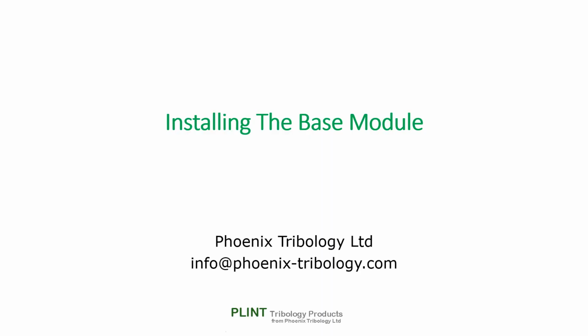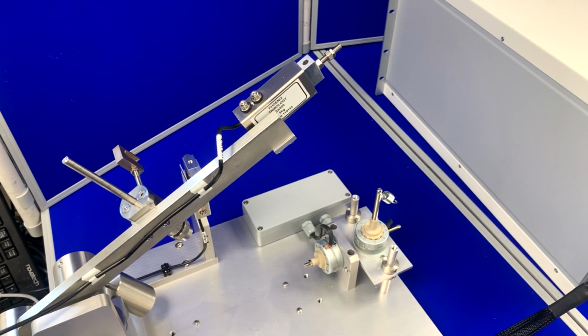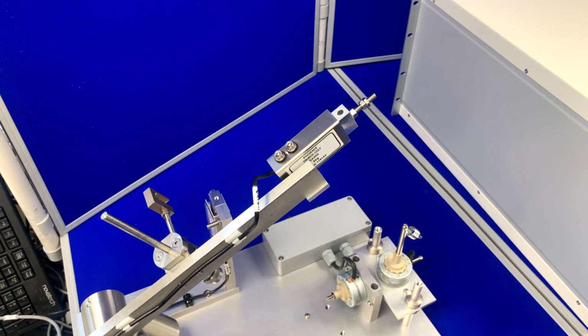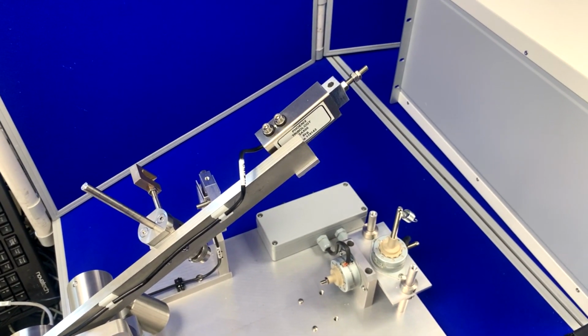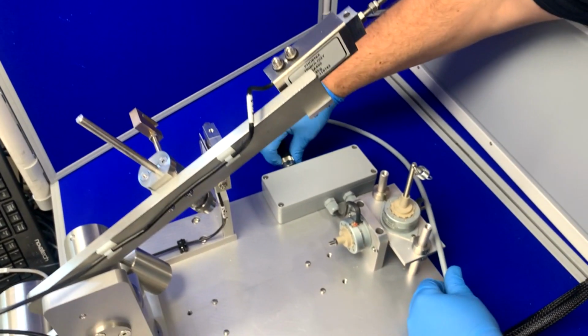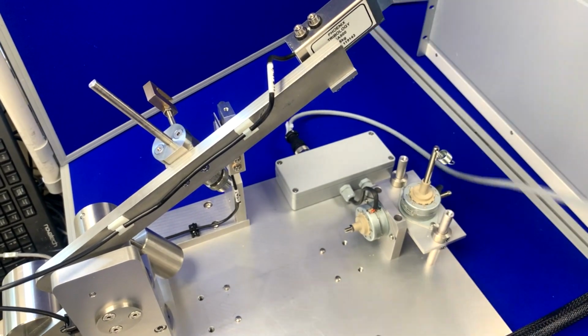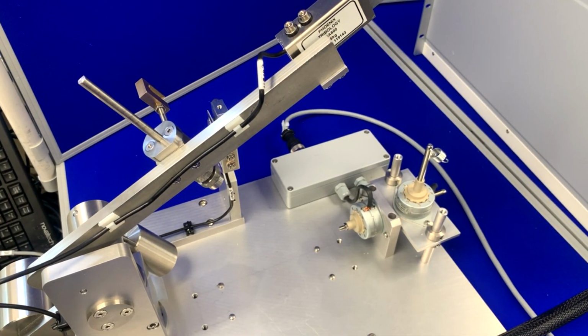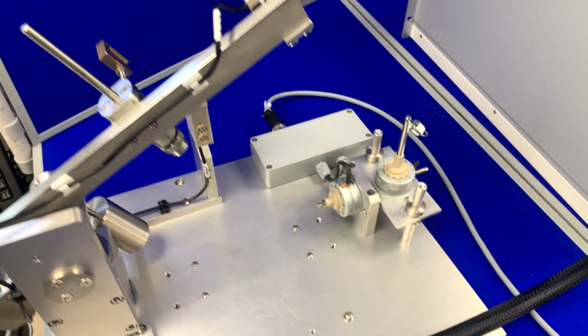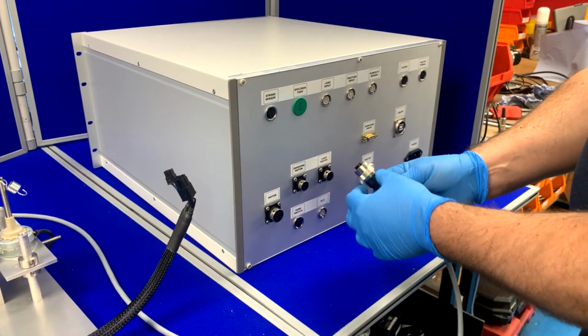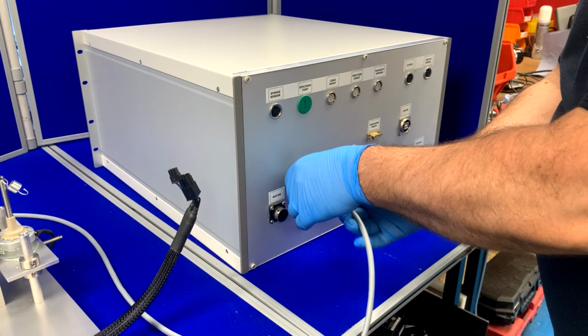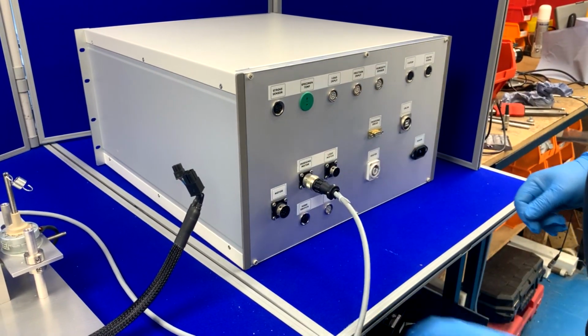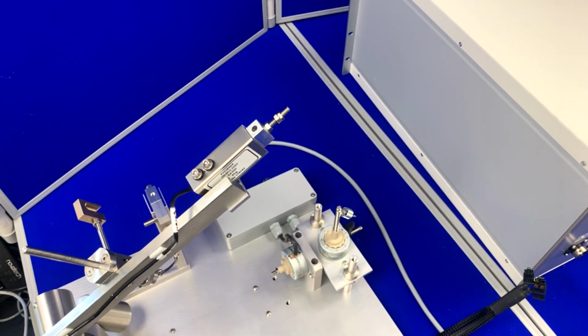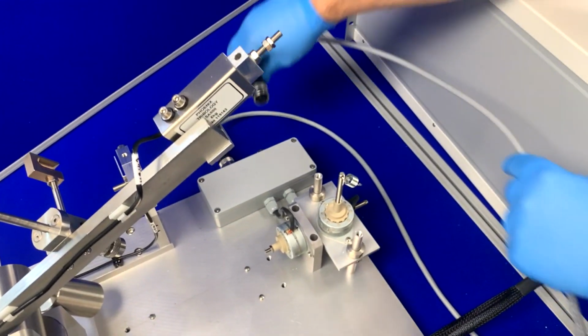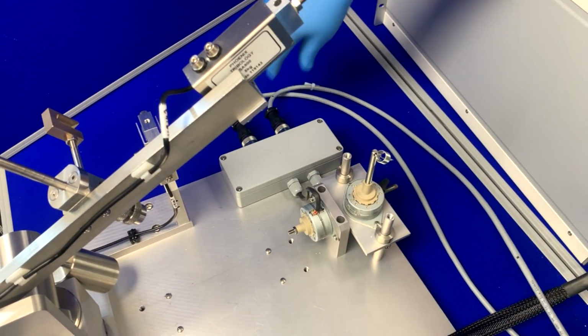To install and set up the machine, start by placing the base module on a solid surface with the control cabinet to the right of the module and the computer to the right of the cabinet. For this demonstration, we have the cabinet mounted back to front. Connect the indexing motor cable to the junction box on the machine and the other end of the cable to the appropriate socket on the cabinet. Do the same for the load motor cable and for the DC motor cable.